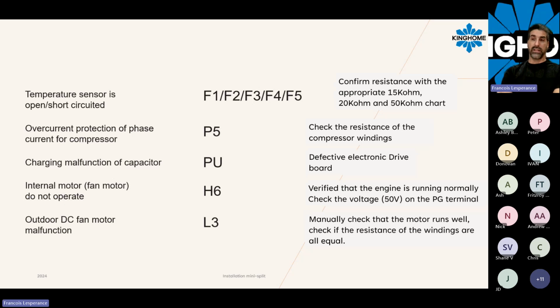L3 is related to the outdoor DC fan motor. This motor is like the inverter compressor. You can check the resistance of each winding, and also make sure it's not grounded.